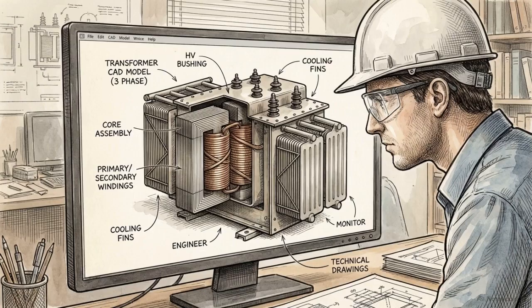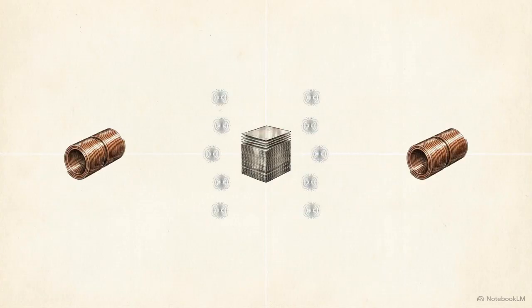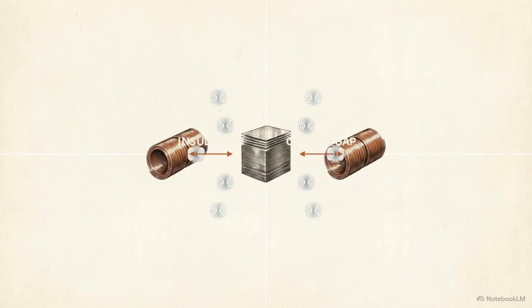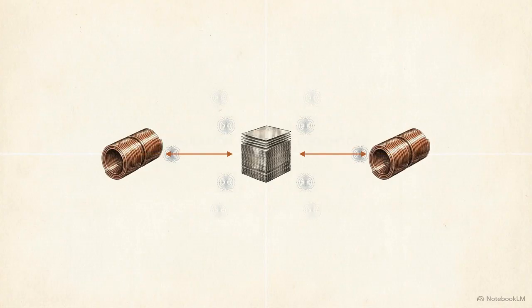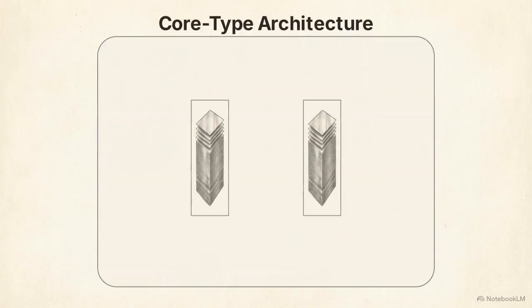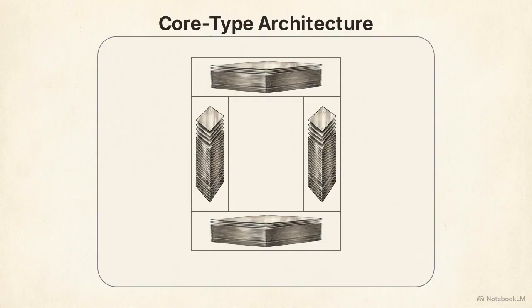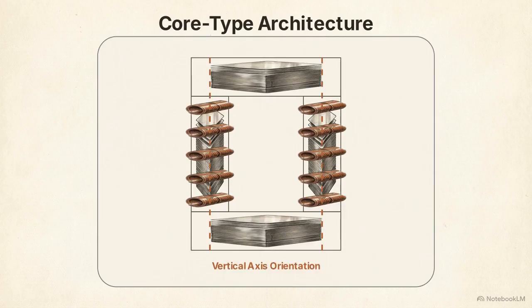This dynamic turns transformer design into a spatial geometry problem. Engineers must maximize the magnetic flux interacting with the coils, while leaving enough physical space for thermal cooling and electrical insulation. To solve that geometry problem, manufacturers bifurcated transformer design into 2 distinct architectural topologies, the core type and the shell type. In the first and most common topology, the core type architecture, the copper windings enclose the magnetic core. This configuration typically utilizes a standard vertical axis orientation for the core legs, allowing flux to travel cleanly up and down the pillars.